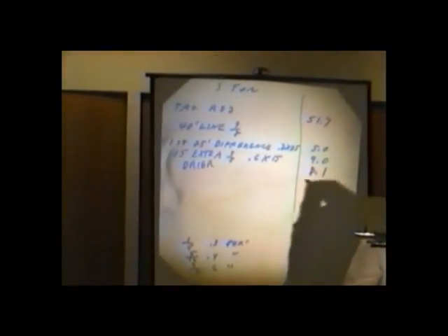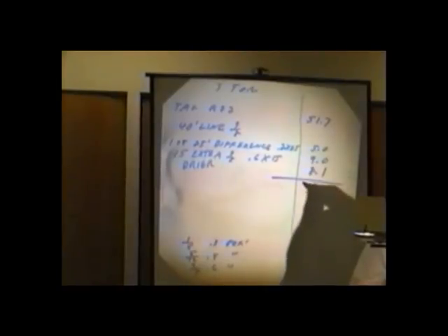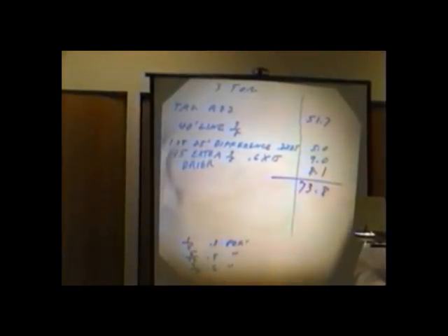All right. So the point is, right now, we know that it's a 3-ton system. We have to also add 8.1. So now we're going to put down dryer. And so let's put down 8.1. And that should be our total system charge. So if I add all that up, let's see, I should have 8. Is this right? I come up with 73.8, am I right?